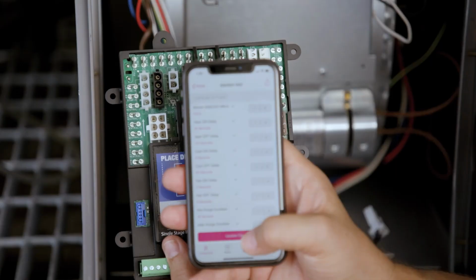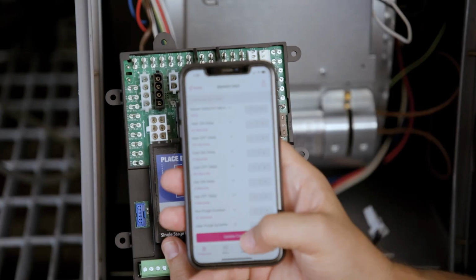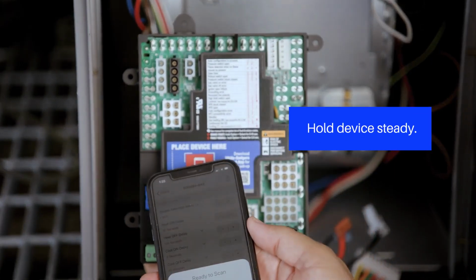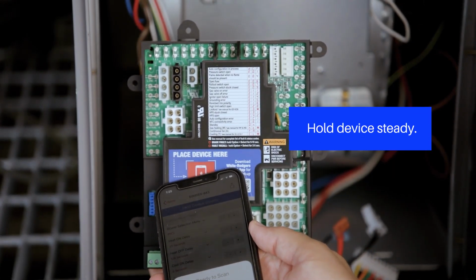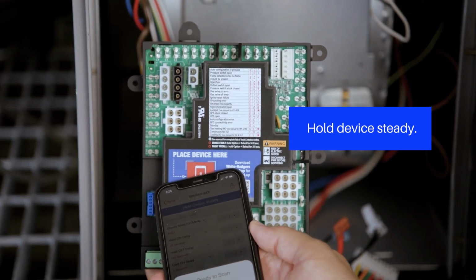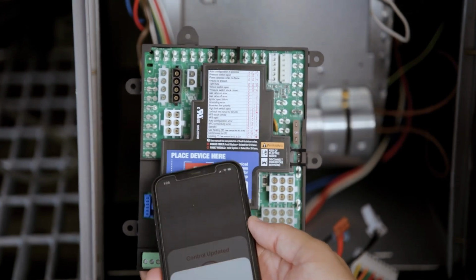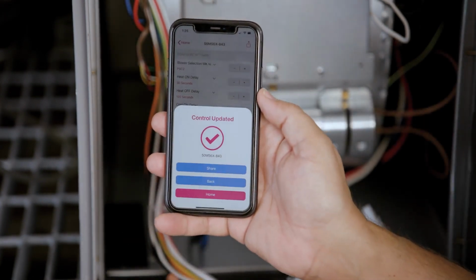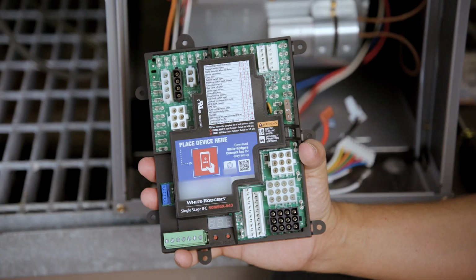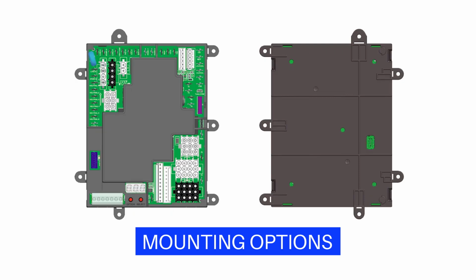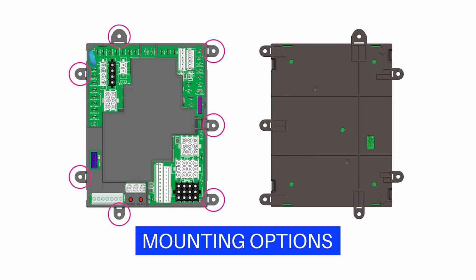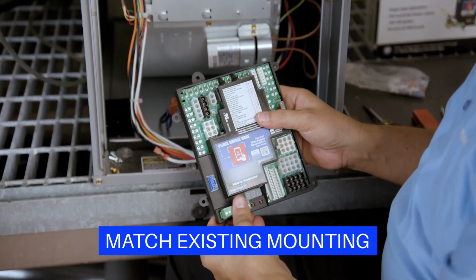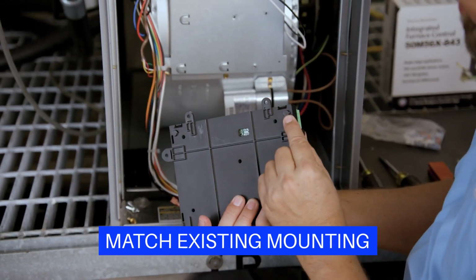For mobile configuration, changes made must be uploaded to the control. Select Update Control and hold the mobile device near the NFC logo. This may take up to 5 seconds. A checkmark will display showing the update was successful. The 50M56X-843 is now ready to be installed. There are 3 styles of mounting options: 7 mounting tabs, 5 standoff holes, and 2 slide-in tabs. Utilize the mounting that matches the existing control if possible.